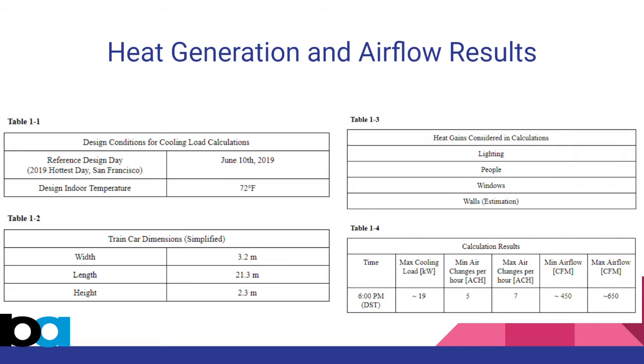If you look at table 1-4, you'll see our actual results from our heat generation and airflow calculations. At 6 p.m. DST in the middle of June, our max cooling load turns out to be about 19 kilowatts. Our minimum and maximum air changes per hour are 5 and 7 respectively. Our minimum airflow and maximum airflow are about 450 and 650 CFM.